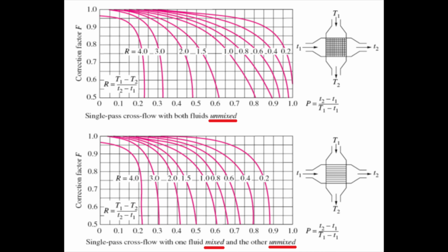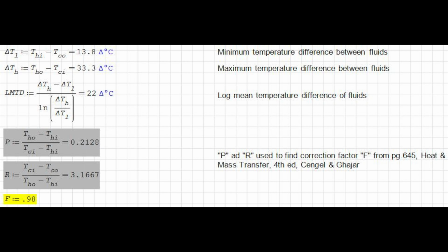In your book, you look up your correction factor for the LMTD method. There's a graph for mixed and unmixed flows. If we find our position, they pretty much all come out in the upper 90%, so this value doesn't really affect much at all. So here I chose a 0.98 off of the graph, and we got a P and R of that, and by looking at the graph, it comes out, like I said, about an F of 0.98.